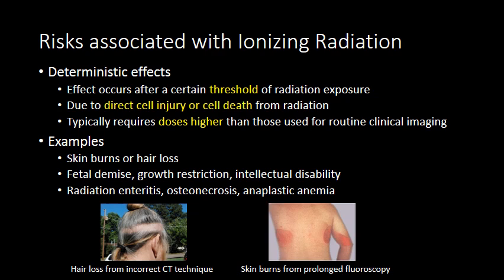The first category is deterministic effects. These are effects that typically occur when a certain threshold of very high radiation is reached. In deterministic effects, the ionizing radiation has caused cellular death or cellular injury from extensive DNA damage. Most of the time, deterministic effects occur at radiation doses much higher than those seen in routine clinical imaging. So if the CT scanner malfunctions or an improper protocol is designed, you may see skin burns or hair loss.